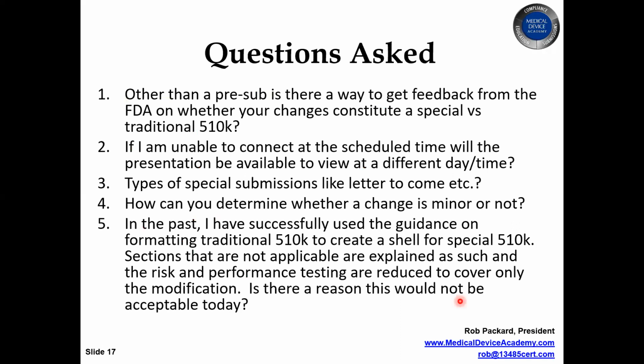However, if you are doing a 510K submission and you know that you've got some modifications planned down the road and you just couldn't get them in for this first submission, that might be a great time, while you're having those interactive dialogues during the substantive review on your first 510K, to mention that this new one's coming, and that's when you get that feedback. If you already have your 510K, it's too late to do that.